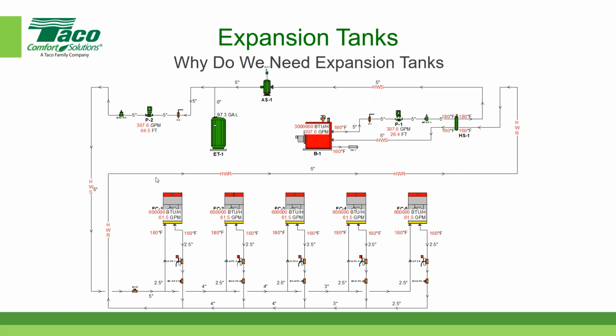If the mechanical room is in the basement, how often did you locate the tank up on the roof or higher to save space? Yeah, if you move the expansion tank from the lowest part of the building to the highest part, the tank becomes physically smaller. That's one of the fundamental principles of Boyle's Law. If you go through the calculations and selection process, you'll find the expansion tank is physically smaller.